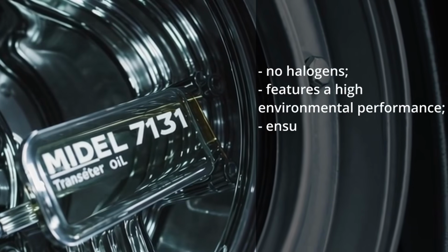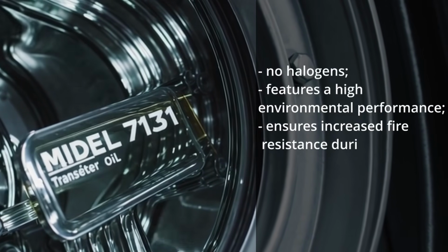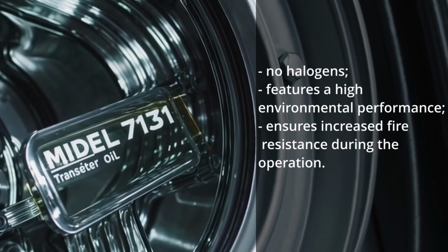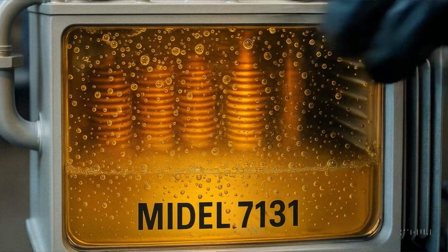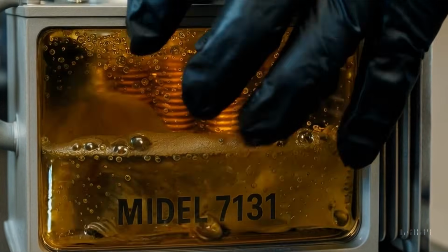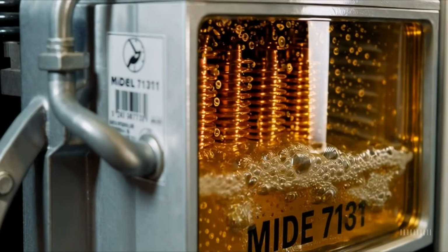One of the distinctive features of MIDEL 7131 is its ability to retain a considerable amount of moisture without significant deterioration of electrically insulating properties. The typical moisture content of this fluid can reach 50 parts per million or more, which is considerably higher than that of mineral transformer oils.